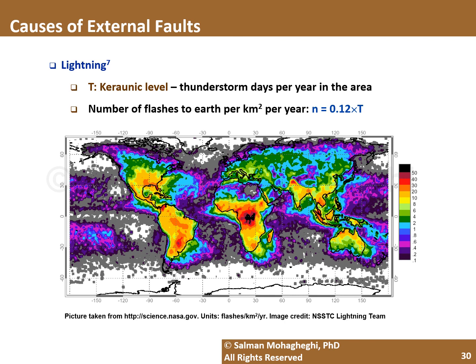Talking a little bit more specific about some of these, lightning is the most common cause of short circuits in power systems. Typically what we do is we look at the geographical area in which the overhead lines, transformers and substations are located, and we identify the frequency of lightning activity in that region. One of the numbers that we typically look at is the keraunic level, which indicates the number of thunderstorm days per year in that area.